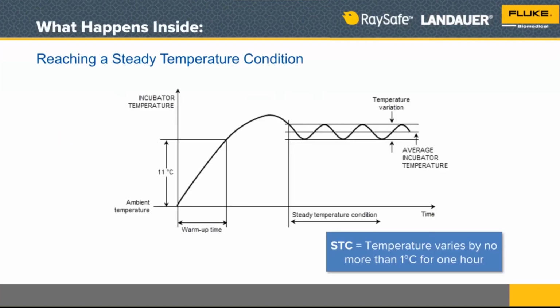So, reaching a steady temperature condition. STC, steady temperature condition, is actually a condition that is achieved after an incubator remains within 1 degree C of its set point for 1 hour. So that means if you're testing incubators, you will need at least 1 hour in order to do that test appropriately and make sure that you've done a thorough job.